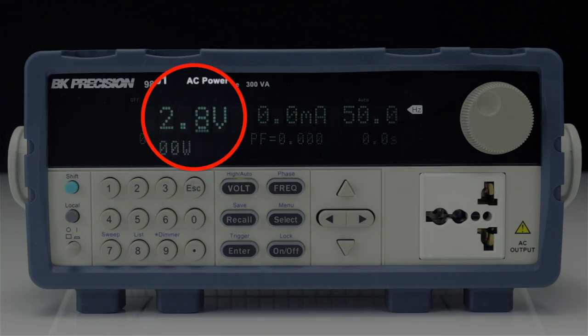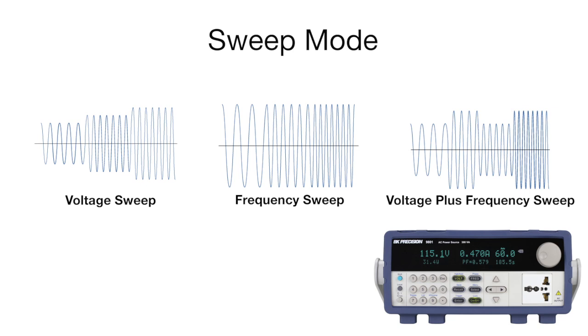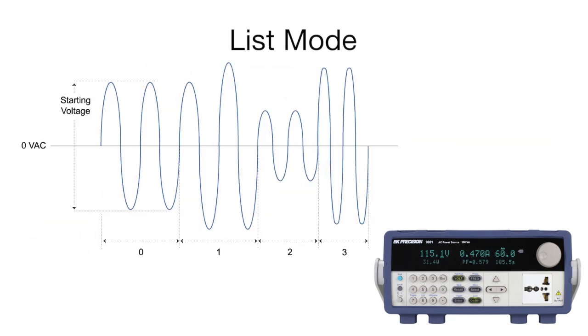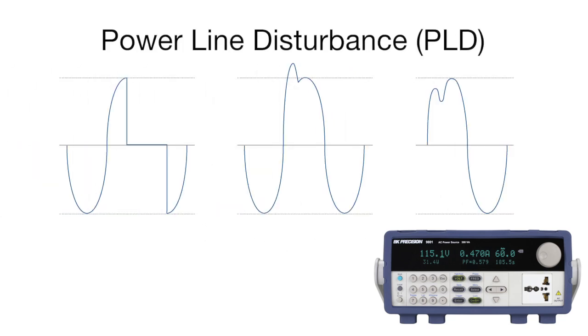Programmable voltage and frequency. Sweep mode settings for sweeping voltage, frequency, and voltage with frequency. List mode for generating complex sequences with varying amplitude and frequency. Extended list mode supports a built-in power line disturbance, also called PLD simulator.